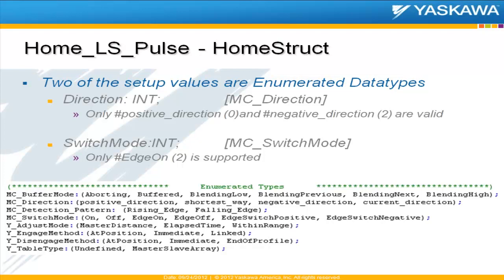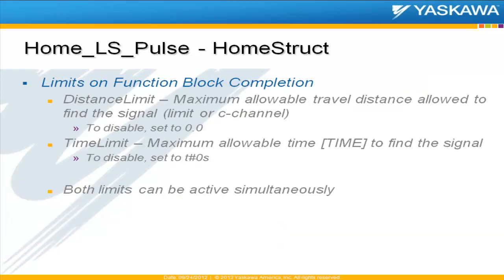There are also two tricky ones in here. The direction is an enumerated data type of MC Direction, and only positive direction or negative direction are valid — that's an integer of zero or two. The switch mode determines how it should respond to the limit switch, and only edge-on is supported, so it's really the rising edge of the switch that will activate this. You'll also notice limits for the approach and creep: a distance limit sets the maximum allowable travel before it aborts, or a time limit — they can be active simultaneously, and either can be deactivated by setting its value to zero.